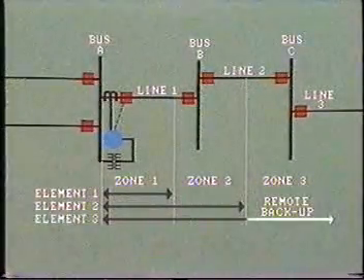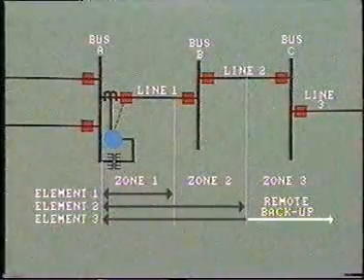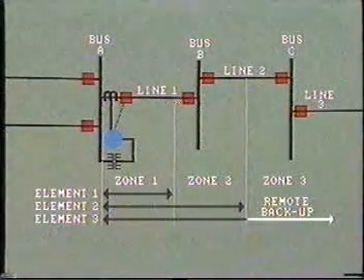Similarly, zone three protection is provided as remote backup for faults along the remainder of transmission line two and on into line three.